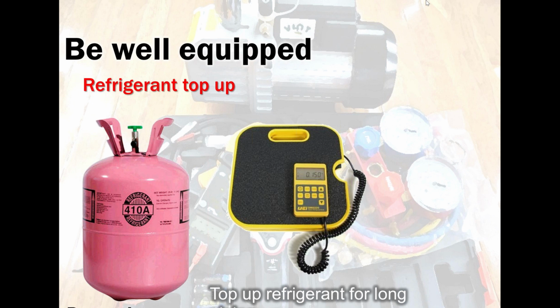Never use the same refrigerant, never. You will not get good results. Please use new refrigerant. If your system was low on refrigerant, recover the refrigerant. There is no harm in measuring how much was inside. But at the end of the day, when you're charging the system, charge with new refrigerant. The composition is perfect as compared to the old refrigerant.